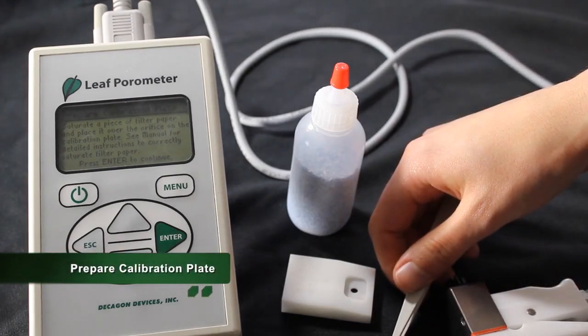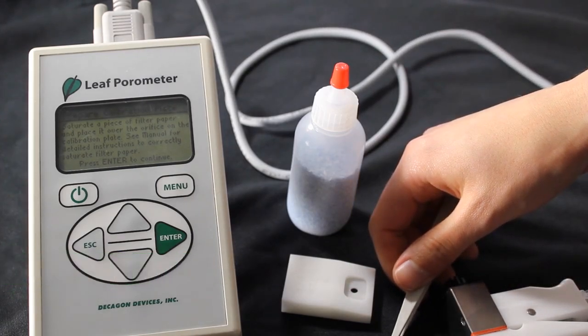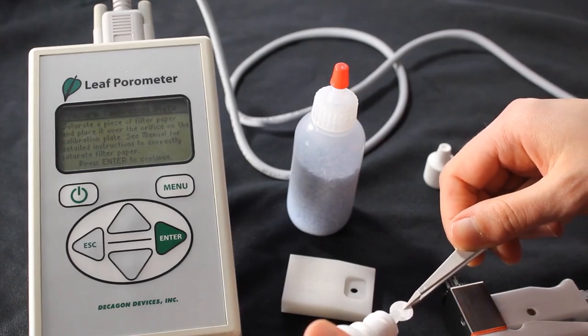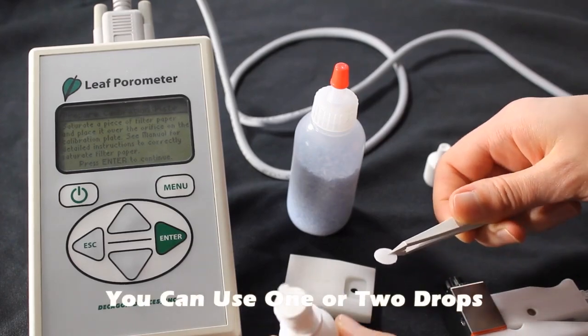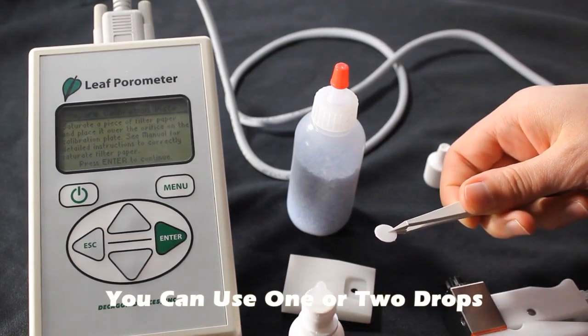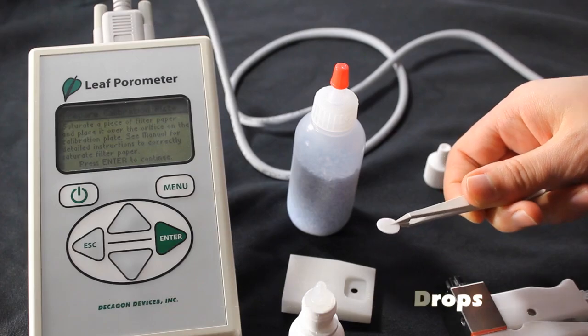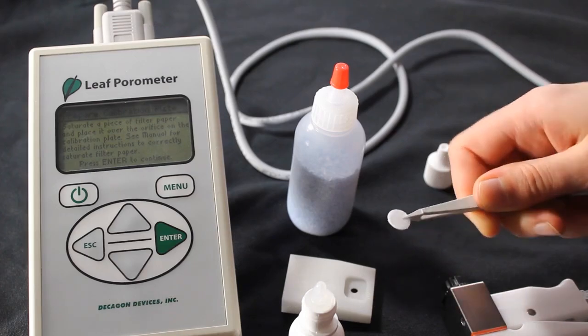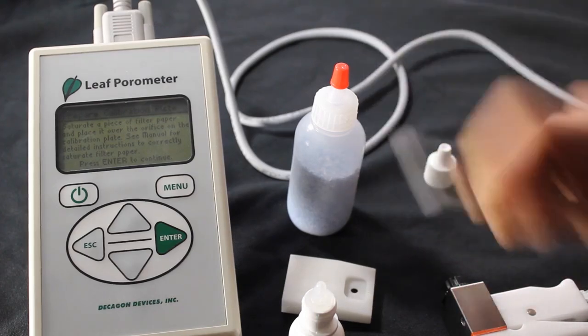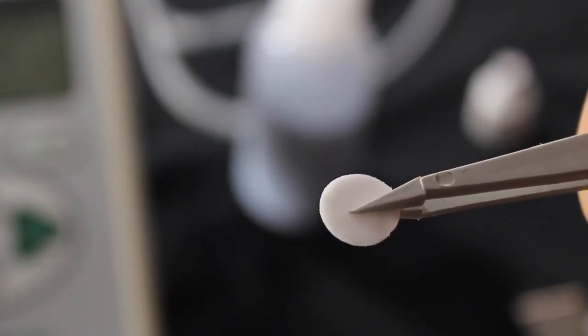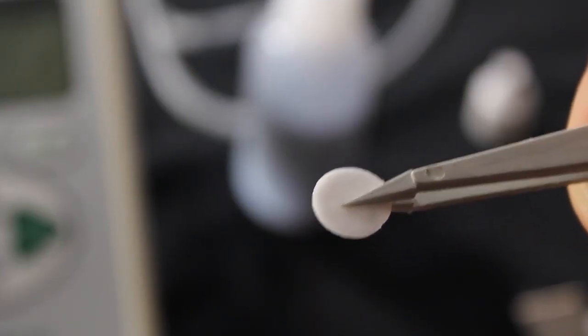The next step is to saturate a piece of filter paper included in your kit. Use tweezers to pick up a disc of filter paper and then add 1 drop of deionized water to saturate it. Allow several seconds for the water to fully saturate the filter paper. The best method of ensuring proper wetness of the filter paper is to use the wet and flick method. The resulting paper should glisten, but there should be no drop of excess water clinging to the disc.